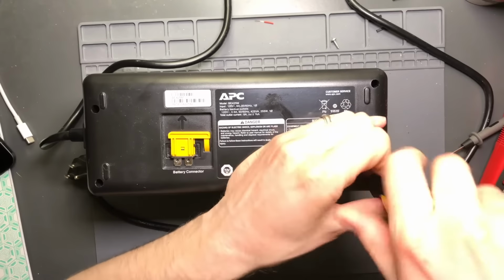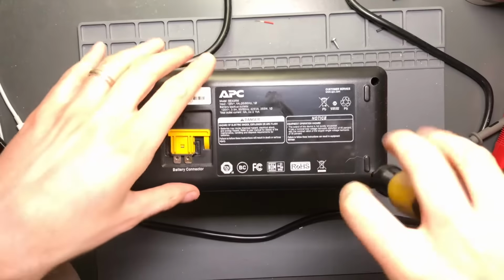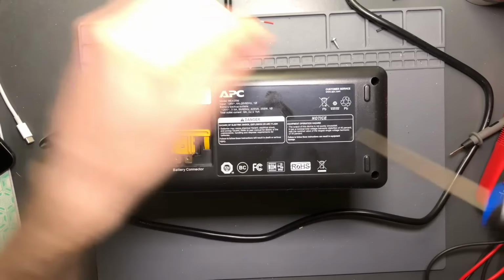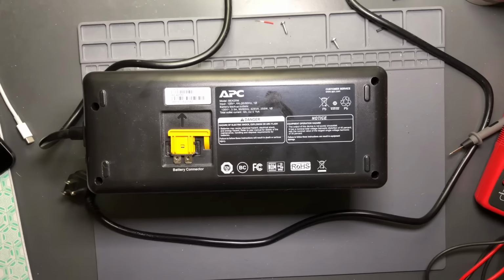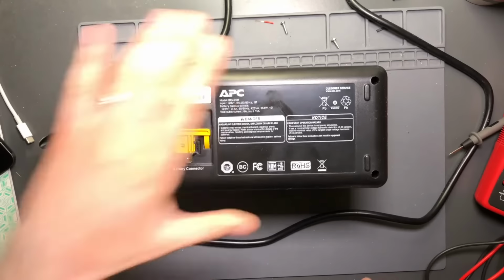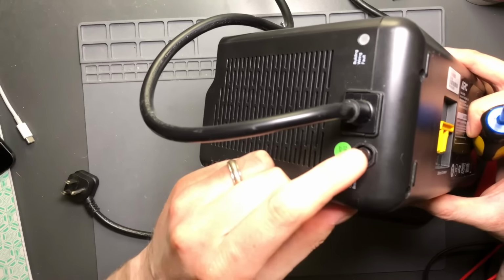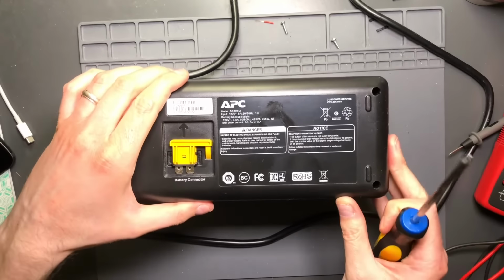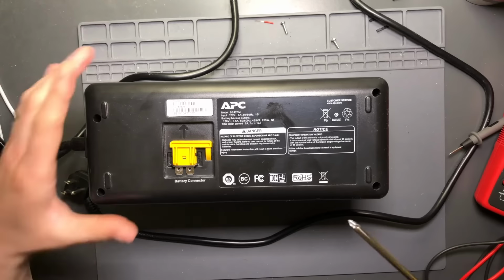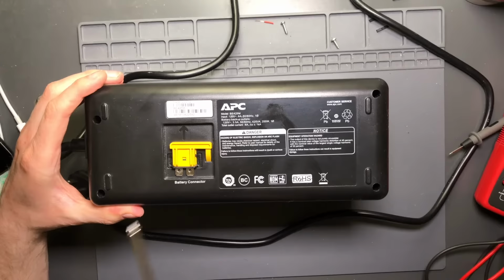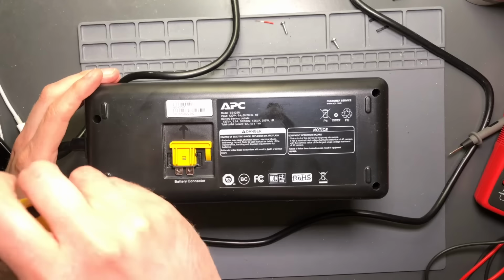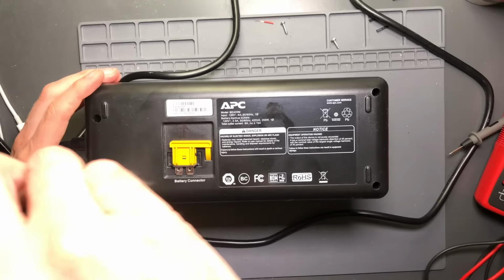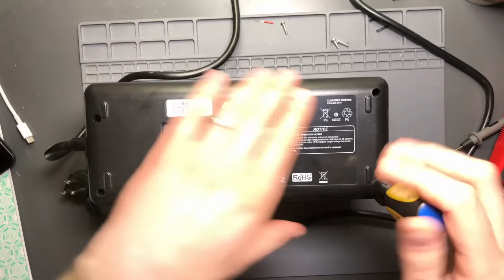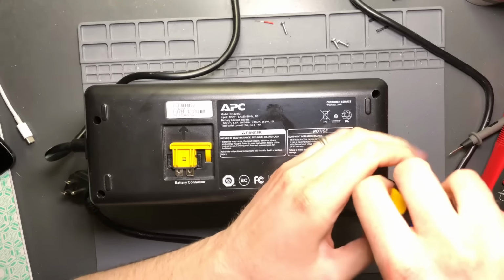This particular one is rated to a maximum input of 7 amps. So if you put it on a 15 amp circuit and load it down to 15 amps, it will pop its little circuit breaker, which it has on this side. Right here, there's a little circuit breaker button, which will pop somewhere above 7 amps. Its battery backup outlets have a total outlet current of 6 amps, though I think it trips at 7, perhaps for derating on over current. The output for the battery backup outlets is 120 volts AC.